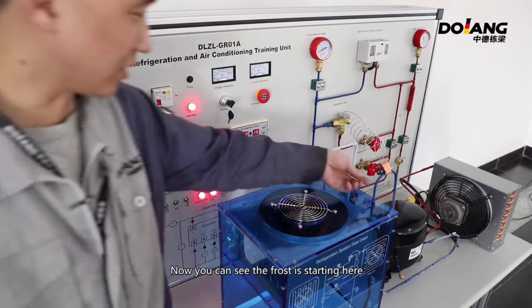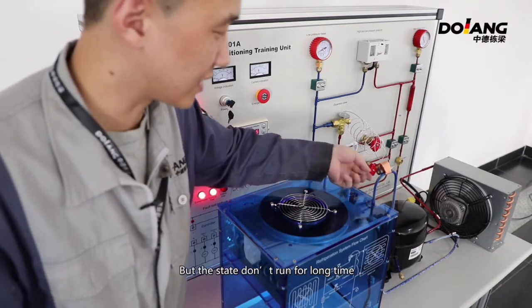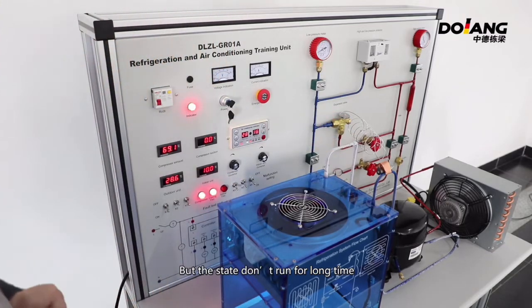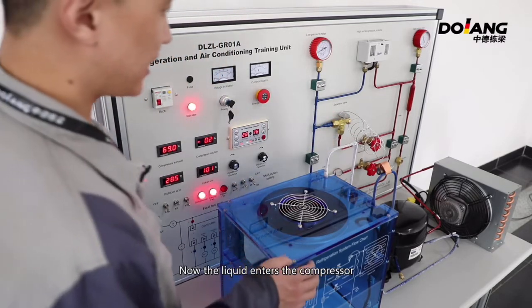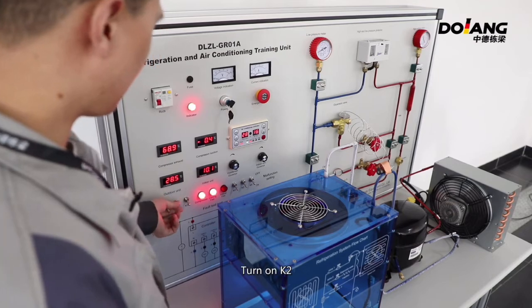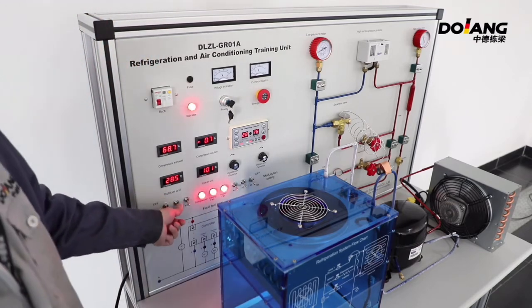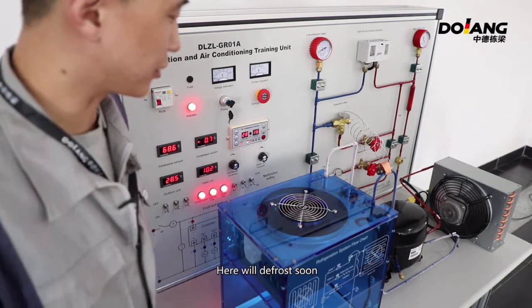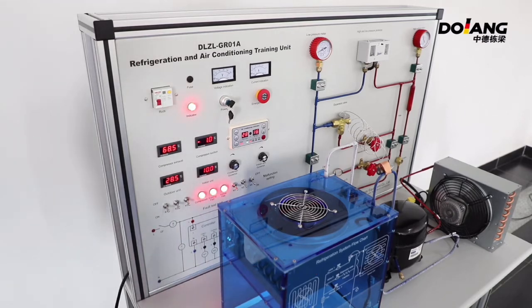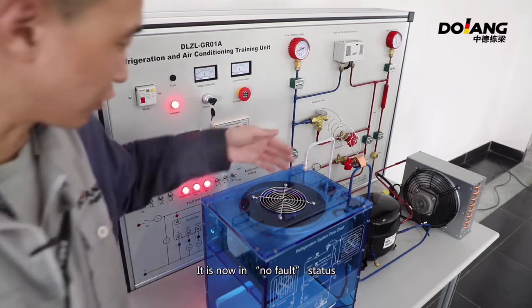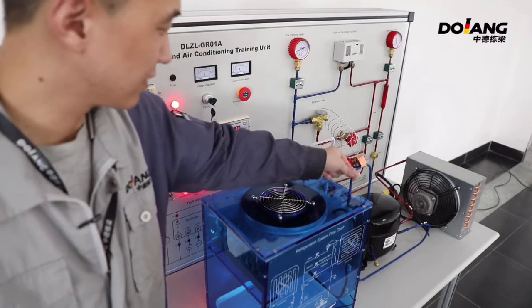Now you can see the frost is starting here, but the state cannot run for a long time. Now liquid enters the compressor. Turn on K2. Here will defrost soon. It's now in no fault status.